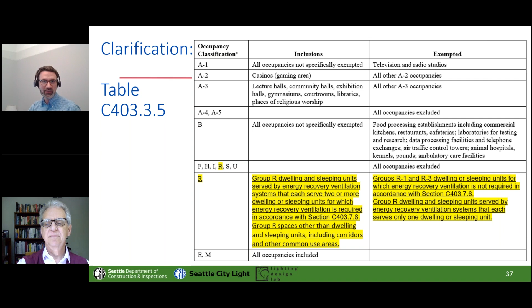I want to speak about the special occupancies. These A3 occupancies are weird ones because they're full of people and then they're completely empty. So for DOAS, it's got to have this ability to ramp up and down. If you do the 62.1 ventilation calc, the area and the people, you get two different numbers, and the area is what you have to do full time, and the area plus people is what you have to do when it's occupied. And a lot of these also have CO2-based controls.